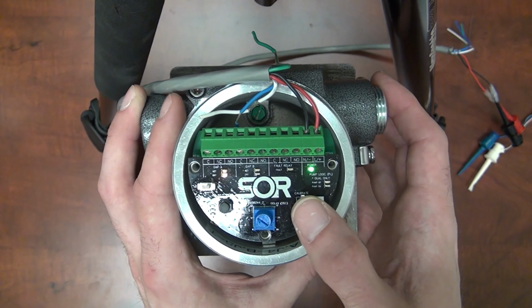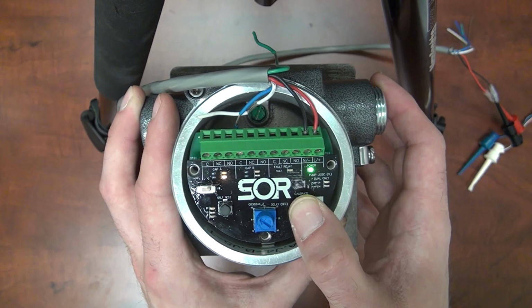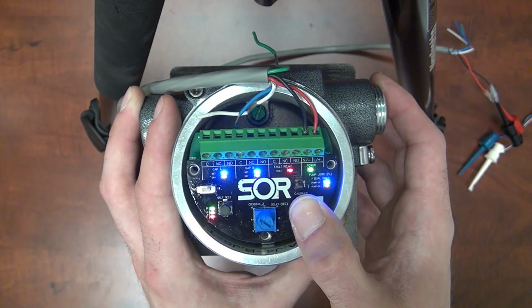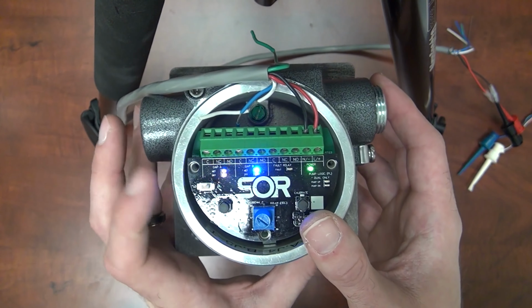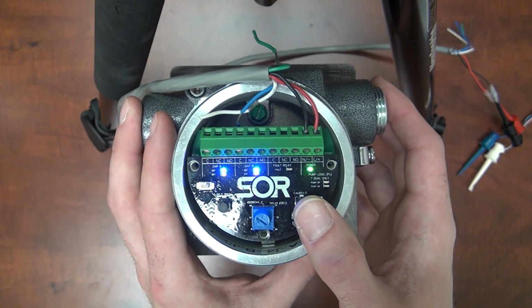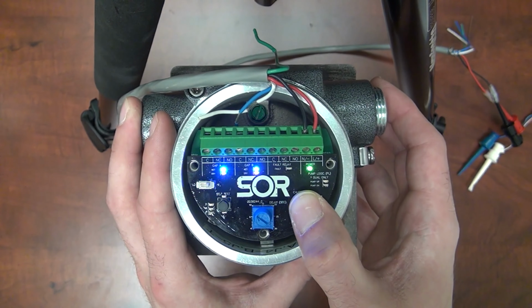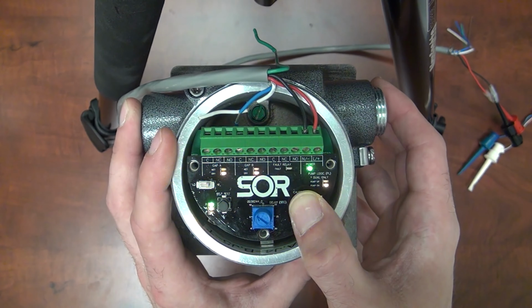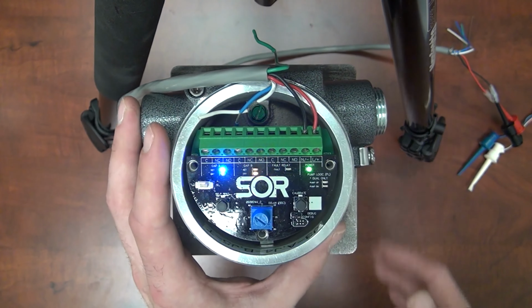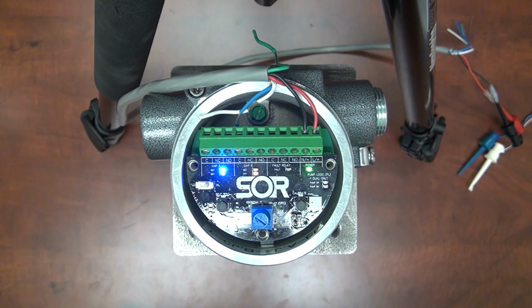So, let's do that. Let's go back into the calibration selection. We're now in selection with the sensorless calibration selected, so let's initiate it. We're going to press and hold the calibrate button again for about 3 seconds. All of the LEDs will begin flashing. Now it can be released. At this point, the device will proceed through the sensorless calibration procedure without requiring additional input from the user.